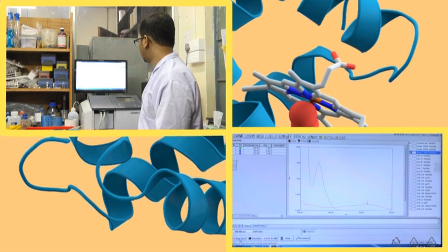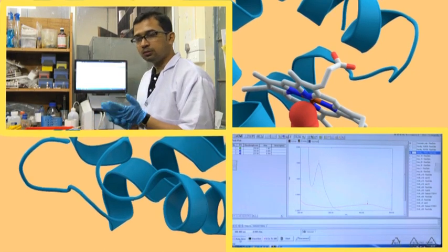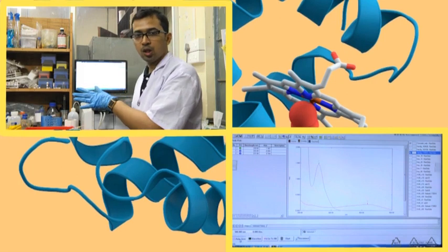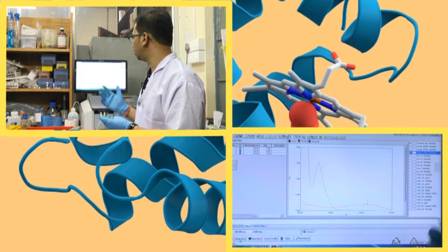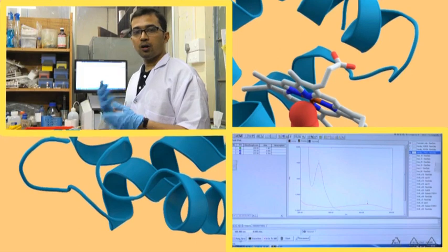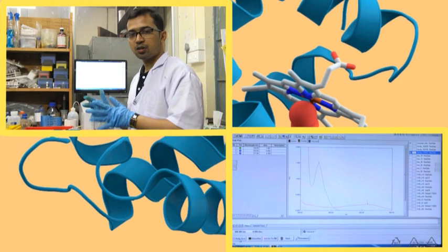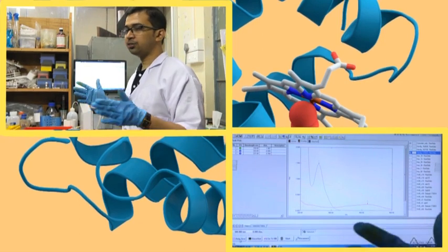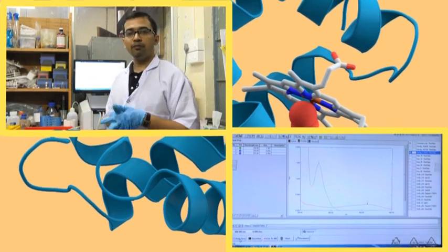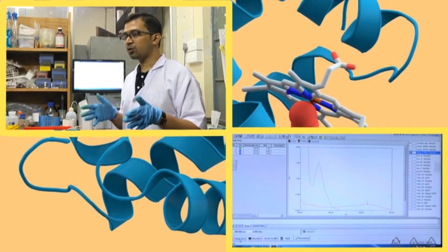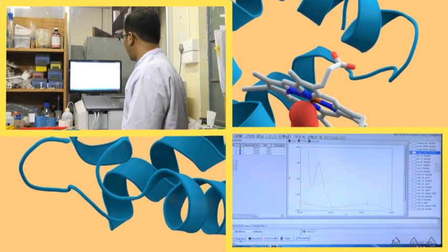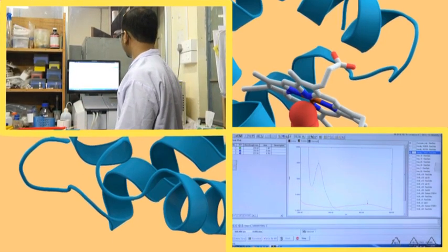We have to do auto 0. For that, let us do auto 0. One thing is that if you change this wavelength range, sometimes some software might ask for baseline correction within that range also. So, you might proceed with baseline correction first. Suppose you change from 600 to 200 to 500 to 200, then you can go for 500 to 200 baseline correction and again go for analysis. Now, auto 0 is done, we will go for start.